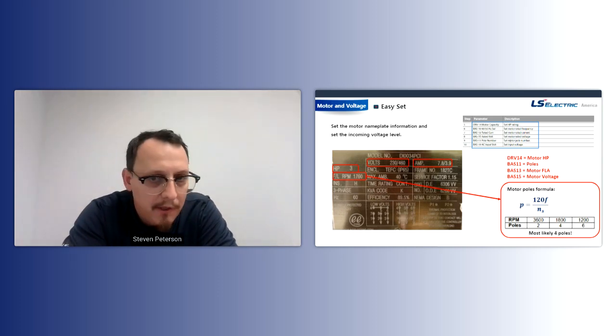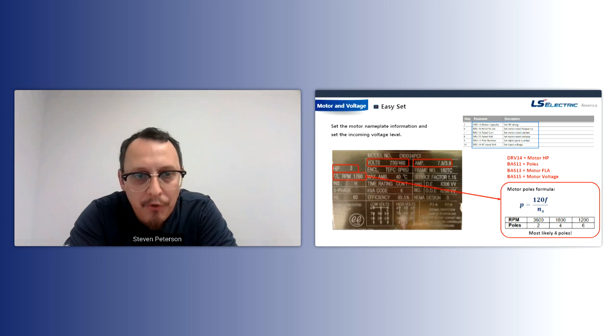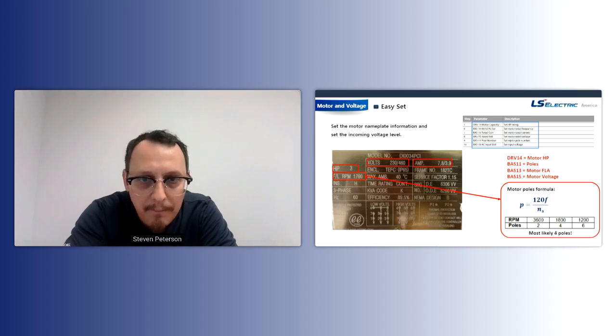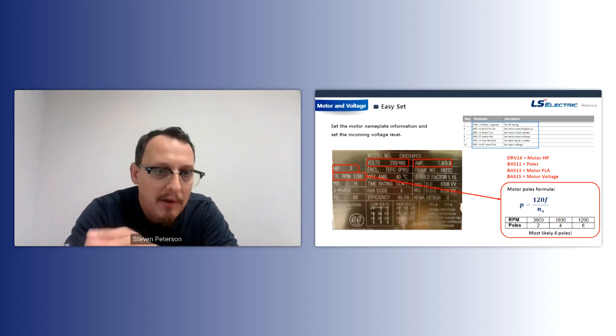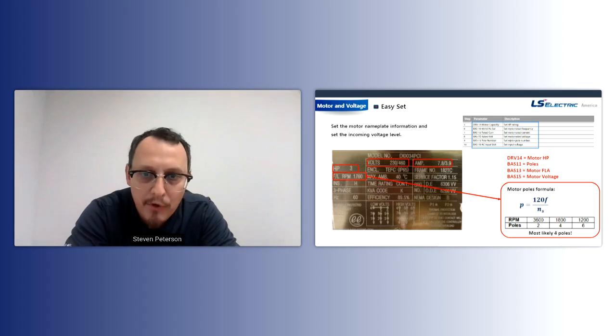So to kind of dovetail into that, you're going to set your incoming voltage and then set accordingly based on what voltage you're running to the motor. Okay, so step 10 here is incoming voltage, which we recommend is reading that with a multimeter and programming it in. And then additionally, you have your number of motor poles.